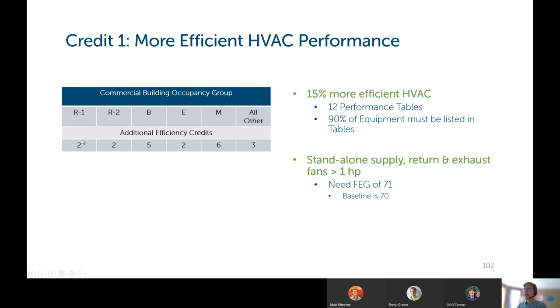And associated to those are the number of credits that you would get towards the 6 that you need to have total. What you need to do to get those points for those different buildings is have at least 15% more efficient HVAC systems based on the HVAC performance tables of the code. And 90% of your HVAC equipment must be listed in those tables that has actual efficiency values. Any standalone supply, return and exhaust fans over 1 horsepower need to have a fan efficiency grade of 71. The baseline is 70, so that's just a slight increase there. So that is the first credit option.